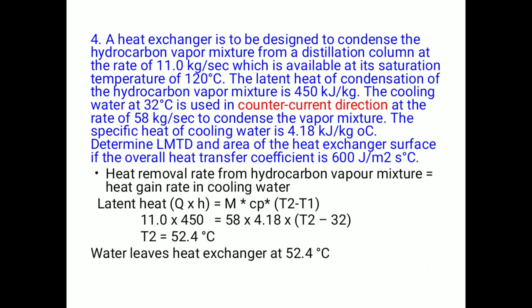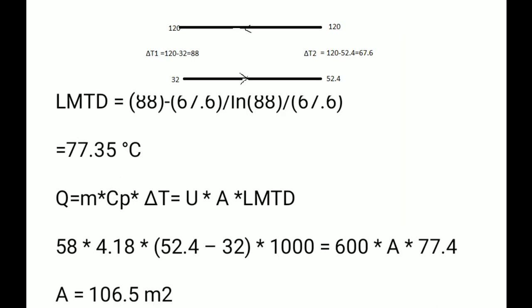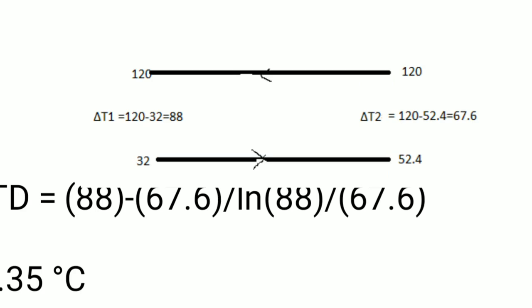The heat gained by the water equals the latent heat released by the hydrocarbon mixture. Latent heat Q = m·L = 11 × 450 = 4950 kW. This equals m·c·ΔT for the water: 58 × 4.18 × ΔT_water. Solving gives the water outlet temperature as 52.4°C.